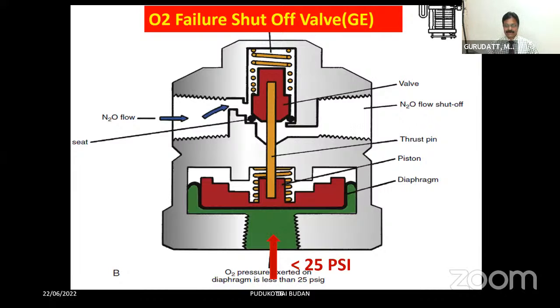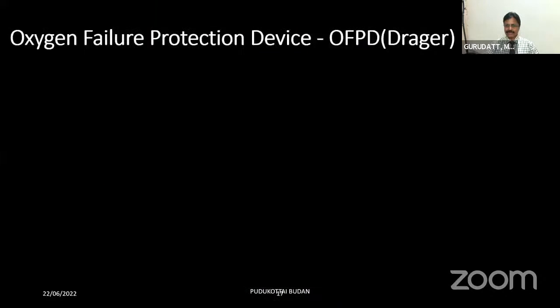So this is an all or none thing. That means till above 25 psig of oxygen pressure, nitrous oxide will be flowing out. You can still use nitrous oxide, but if the pressure of oxygen falls less than 25 psig, you'll not be able to use nitrous oxide, but you can still continue to use oxygen. So that is the shut-off valves. Now coming to the oxygen failure protection devices that are there in majority of the Draeger workstations.